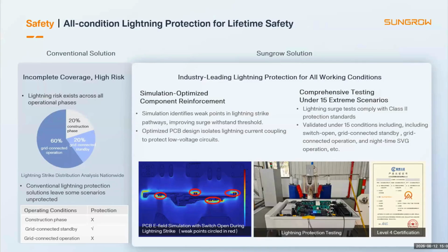Utility PV plants face lightning risk during construction, standby, and normal operation. We validate lightning protection under 15 extreme operation scenarios. Simulation is used to identify weak points in the lightning path, and PCB design is optimized to protect sensitive circuits. The goal is full lifecycle protection rather than protection under only one operating condition.